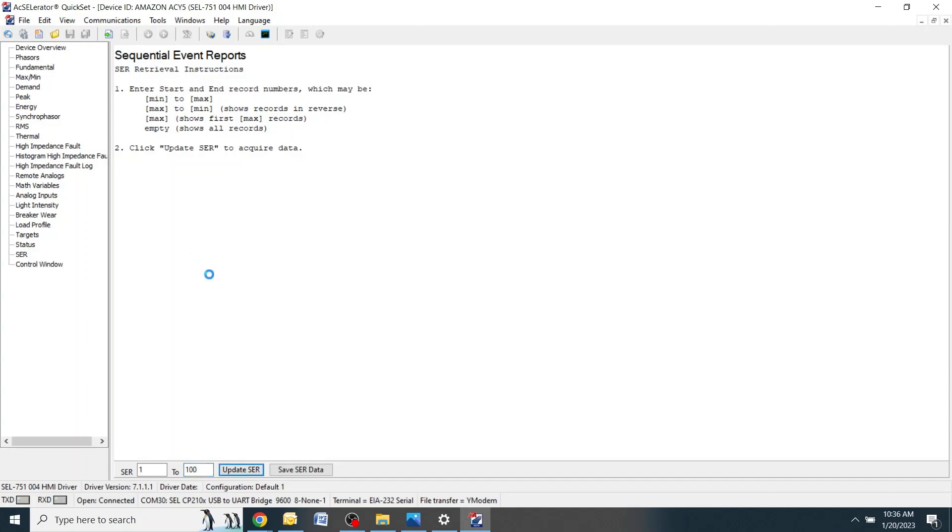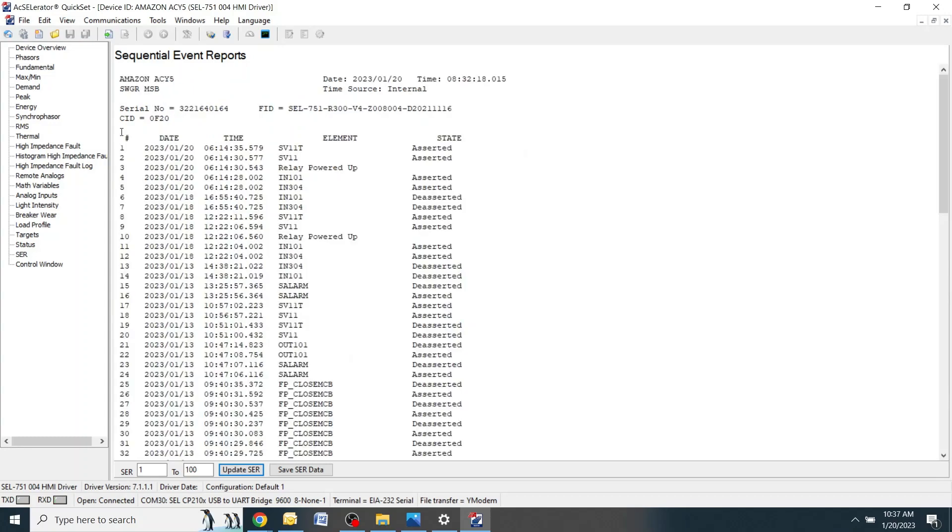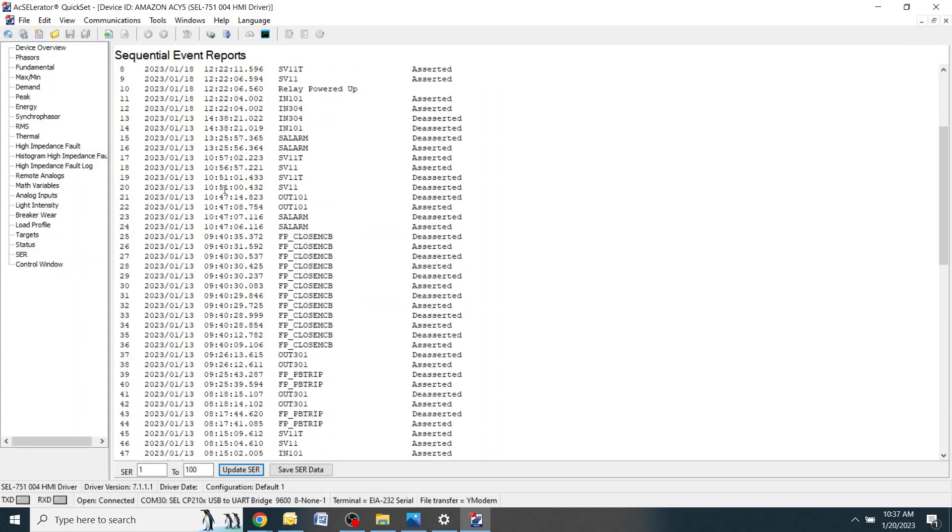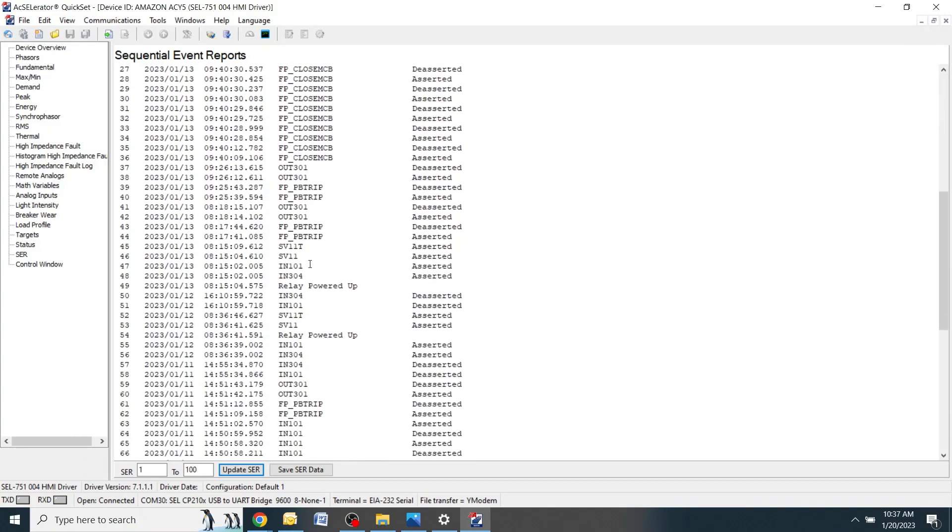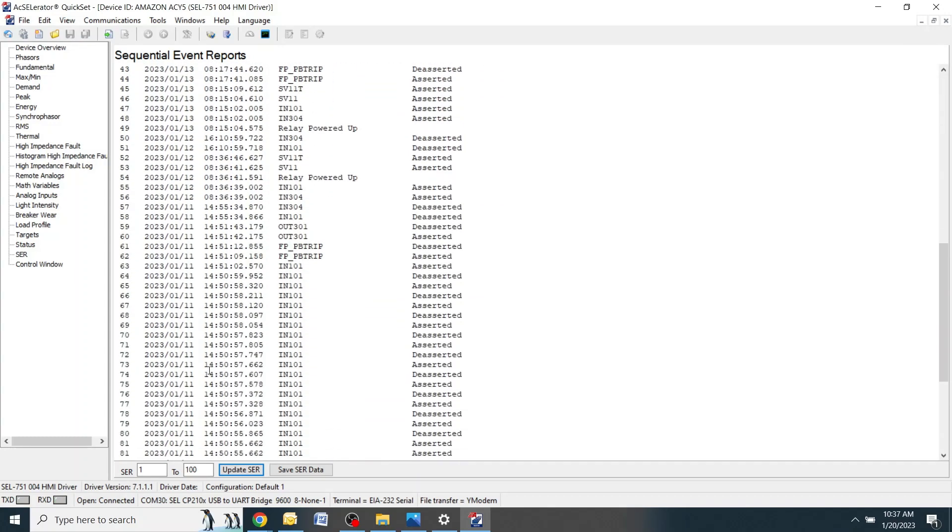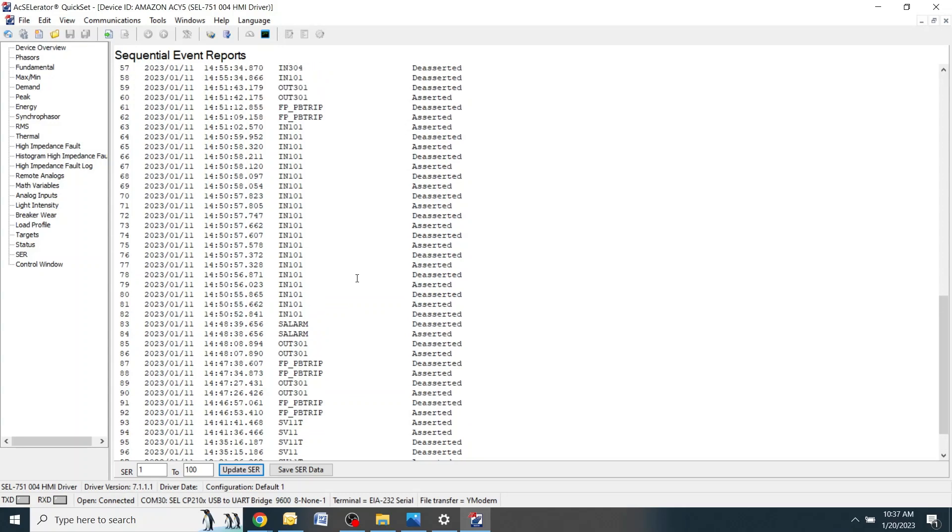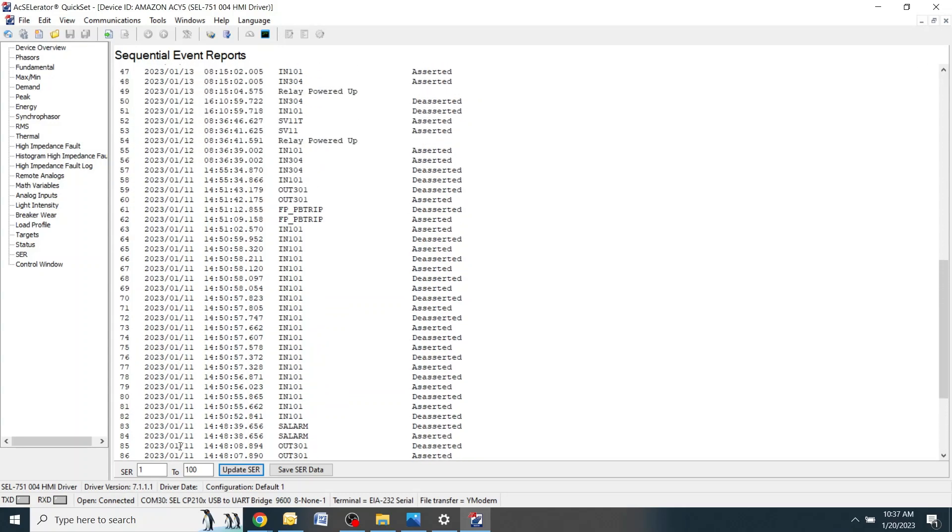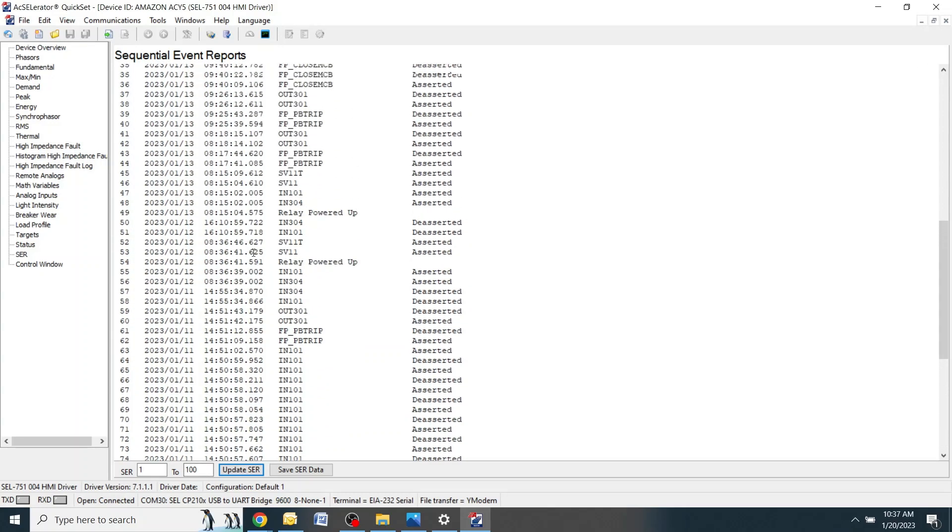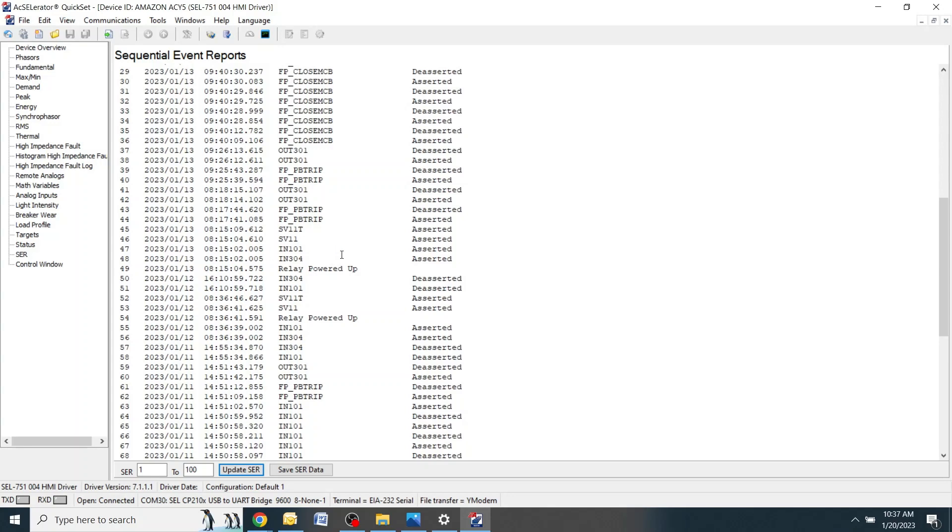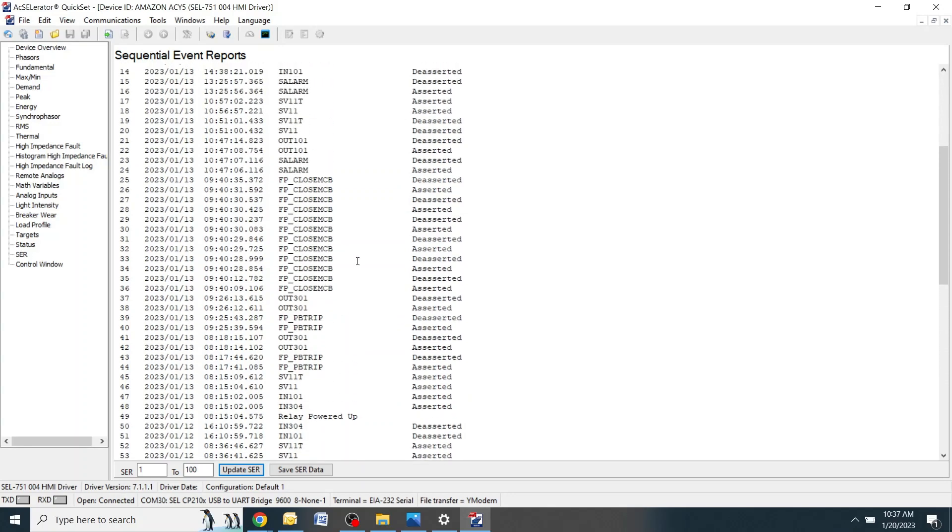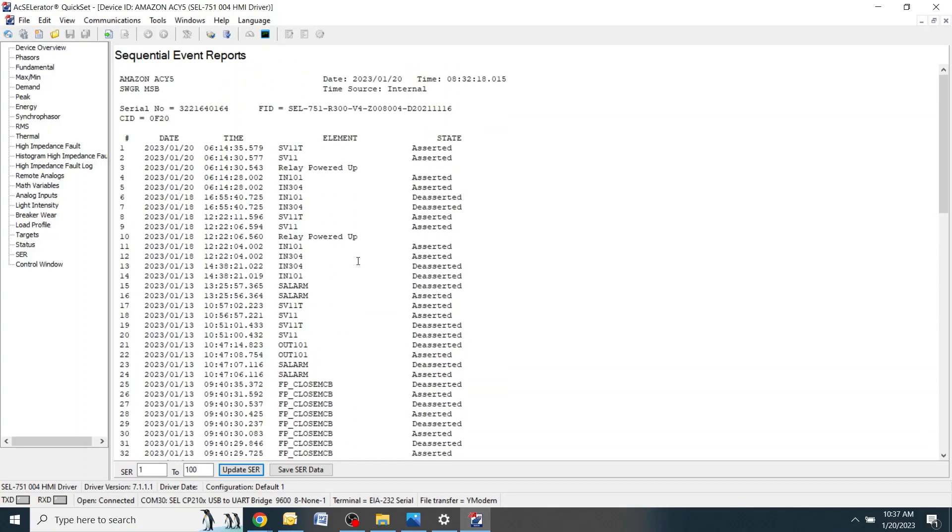Give this a second to load as it's pulling a ton of information from the relay. Scroll down and verify the amount of SER events. In this case there are 100 listed here which most likely means that there are more than 100. If you type in 100 down here and only 43 pop up, that means that there are only 43 SER events saved in that particular relay. When you're ready to save the file, come down here and click save SER data.